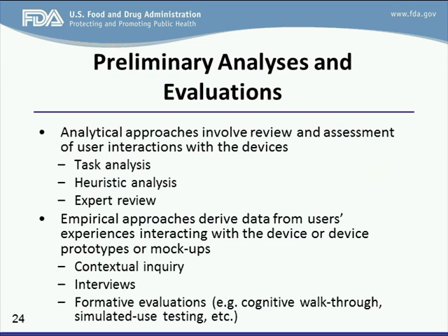Then in the evaluation, you want to start looking at analytical approaches to work through your user interface and understand all of the pieces of safe use. And so that could be through task analysis or heuristic analysis, as well as an expert review. But then the next level, as you're starting to develop prototypes, is to go through contextual inquiry or interviews or formative evaluations, so cognitive walkthroughs or simulated use testing at some level there. And again, each of these are targeted at slightly different pieces of information, slightly different understanding of your user interface. So depending on what you're trying to discover at this point is the method that would be the best for you. So we tried to explain some different options here.